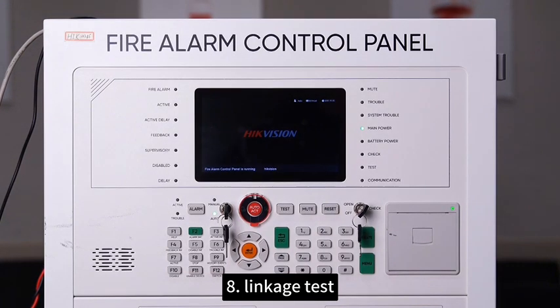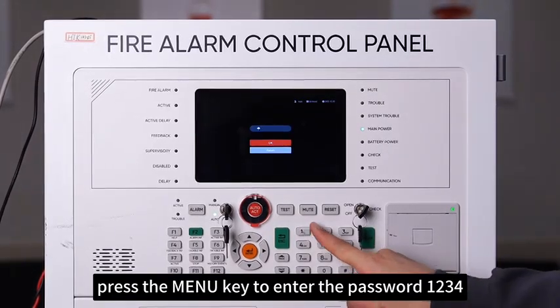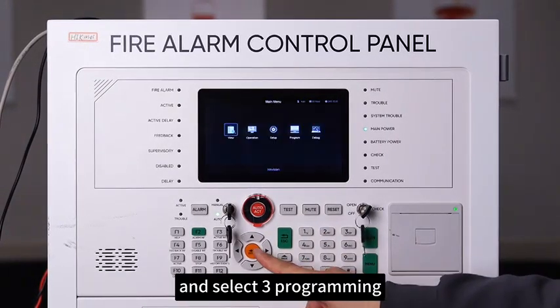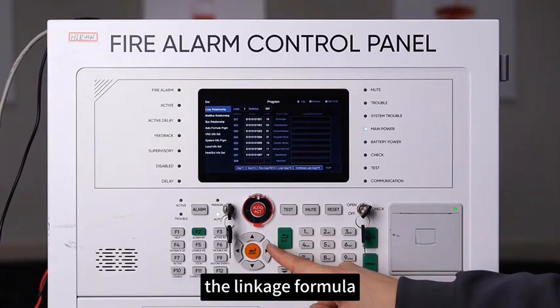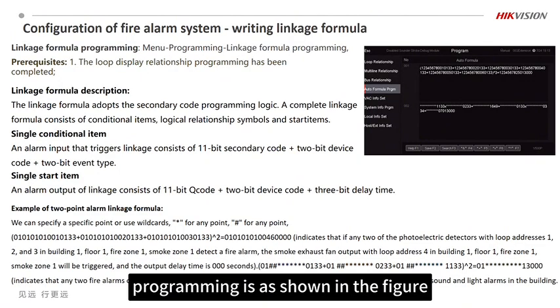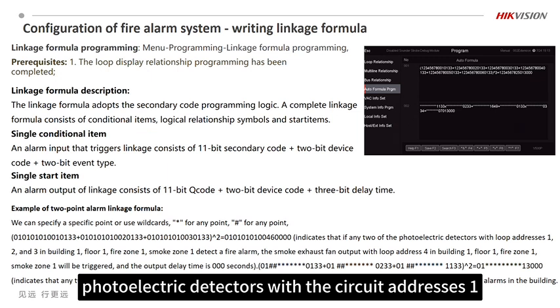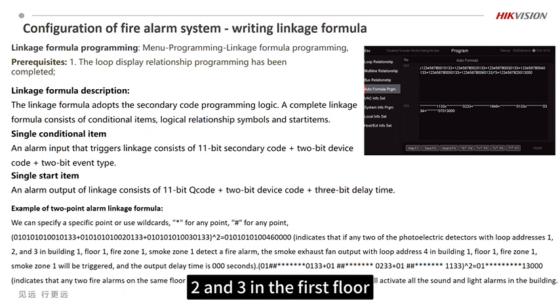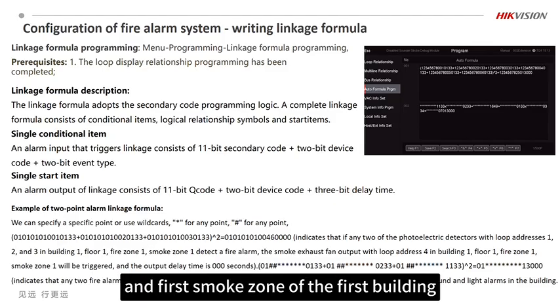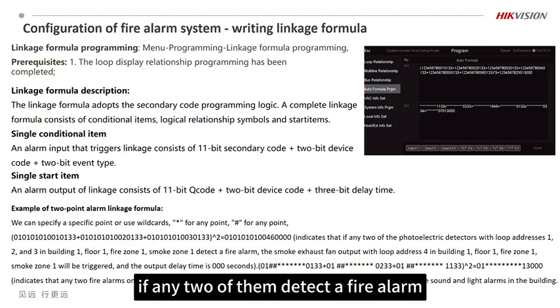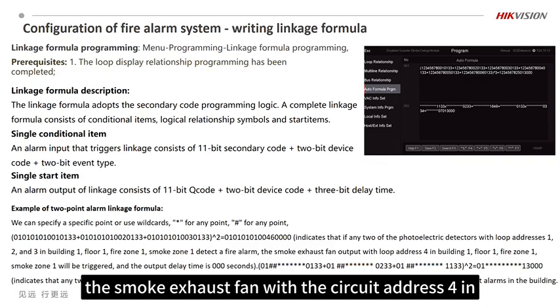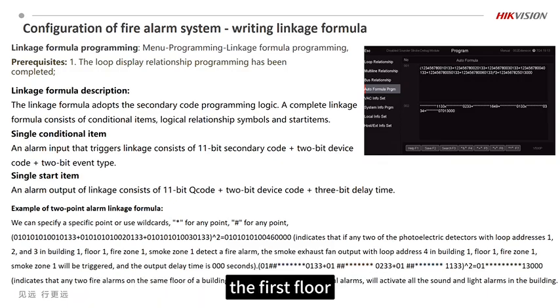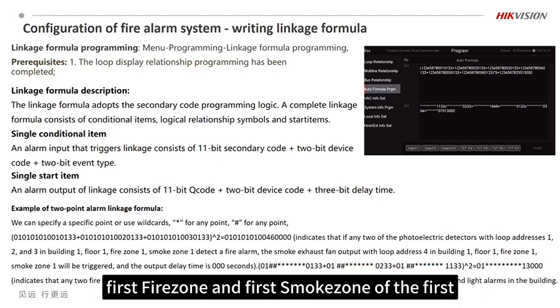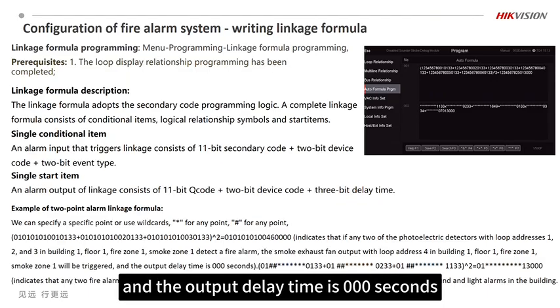8. Linkage test. Press the menu key to enter the password 1234 and select 3 programming. The linkage formula programming is as shown in the figure. It means that the photoelectric detectors with the circuit addresses 1, 2, and 3 in the first floor, first fire zone, and first smoke zone of the first building, if any 2 of them detect a fire alarm, the smoke exhaust fan with the circuit address 4 in the first floor, first fire zone, and first smoke zone of the first building will be triggered, and the output delay time is 000 seconds.